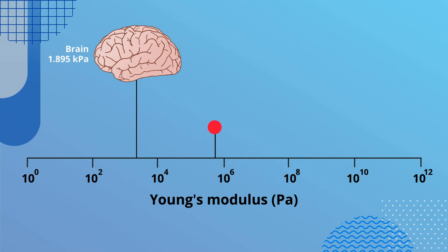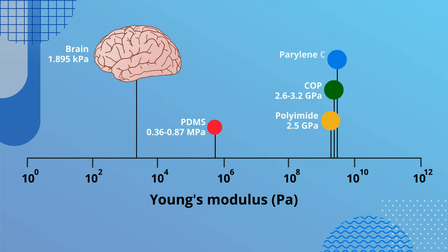The material properties, such as Young's modulus of the probe, should be as close to brain tissue as possible to prevent further damage when the cells undergo micro-motion as a result of movement, blood flow, or breathing.